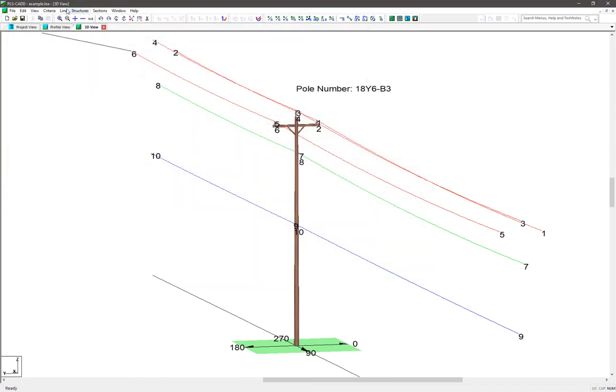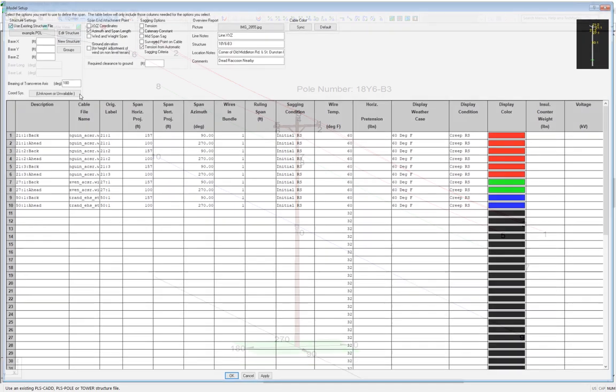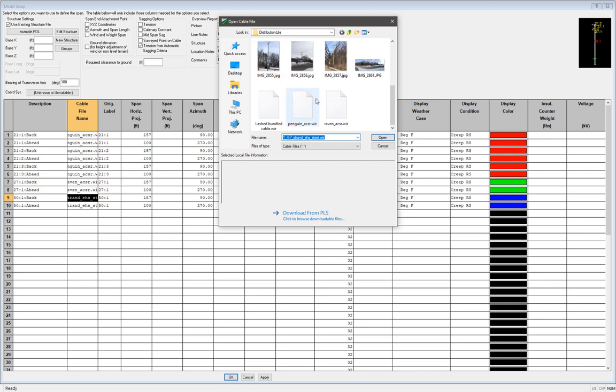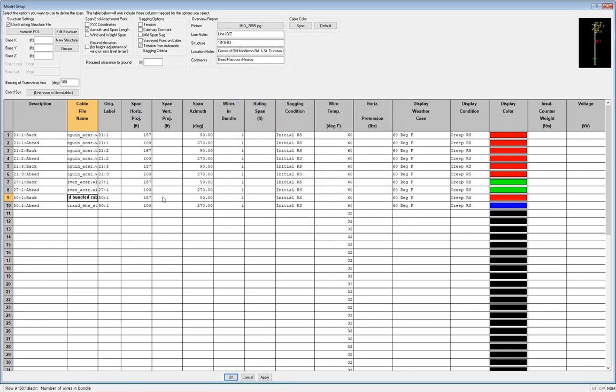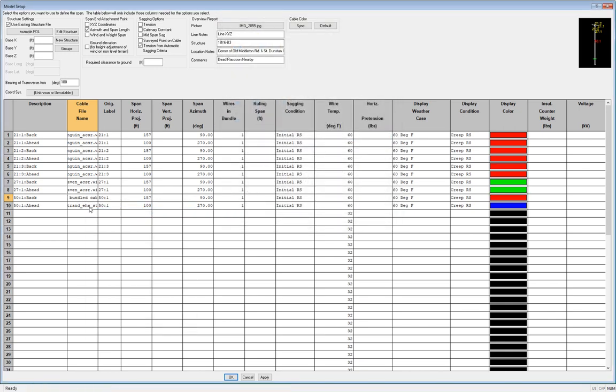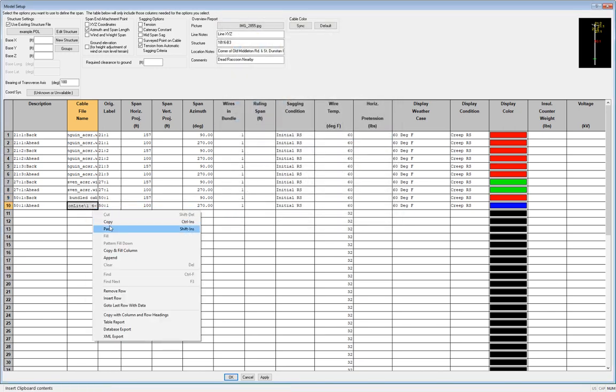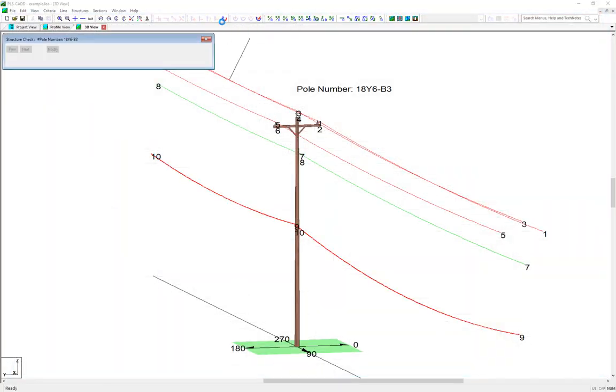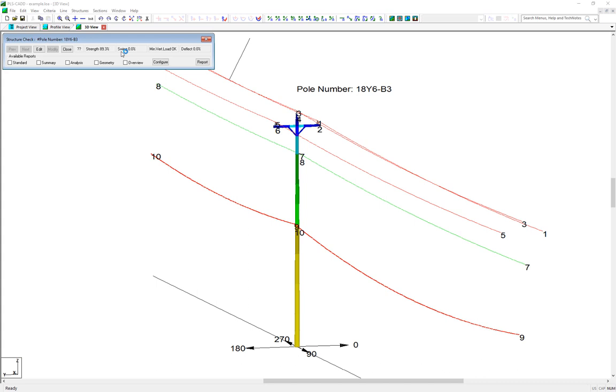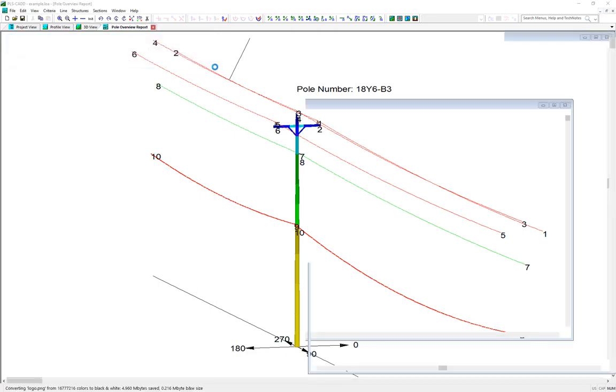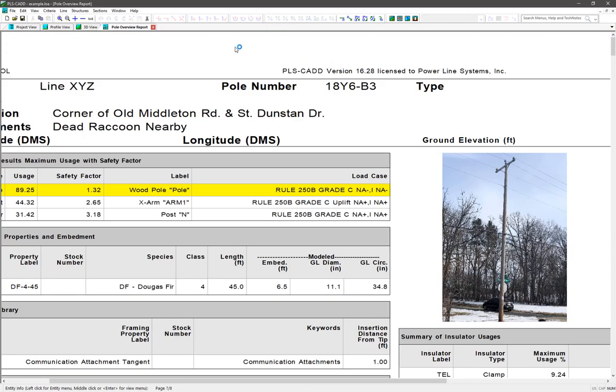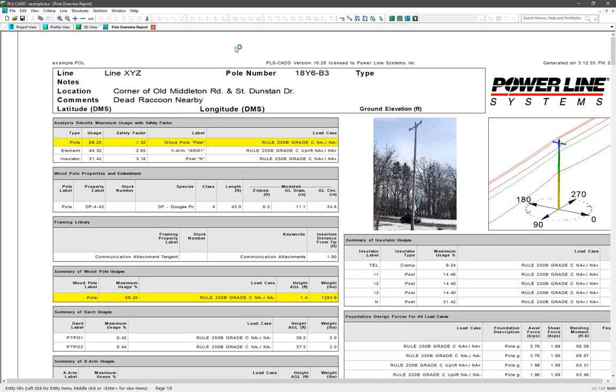Now we go back to the line setup table, and we change out the communication cable to be the correct bundled cable file we just made. Now we can analyze the structure just by clicking this check button here. We can see that it's utilized to 89.3% of its allowable capacity. And if we choose the option to run an overview report, we can see a nice-looking graphical report that shows us all of our general information at the top, gives us an actual picture of the pole, and a colorized utilization picture next to it.